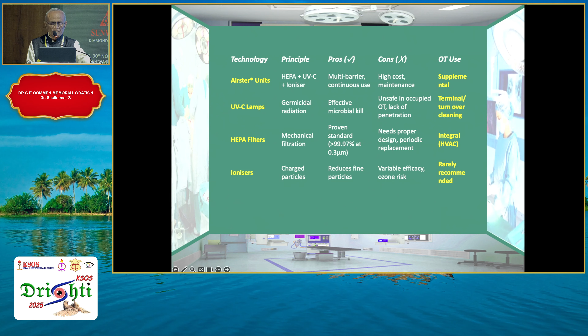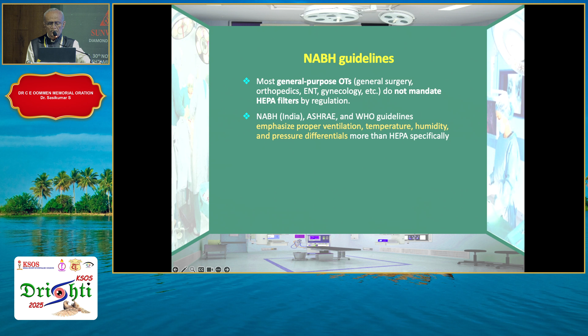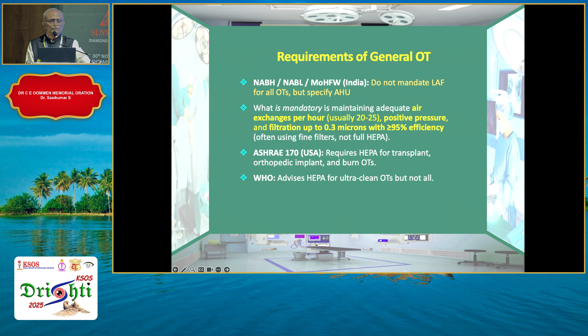What do the accreditation agencies say? As per the NABH, OTs are general or super specialty. And NABH mandates AHU for all OTs. IOTs are general OTs, where they emphasize proper ventilation, temperature, humidity, and pressure differentials. And LAF is not mandatory in IOT, but adequate air exchanges per hour, positive pressure, and filtration rate are mandatory, for which you need an AHU.